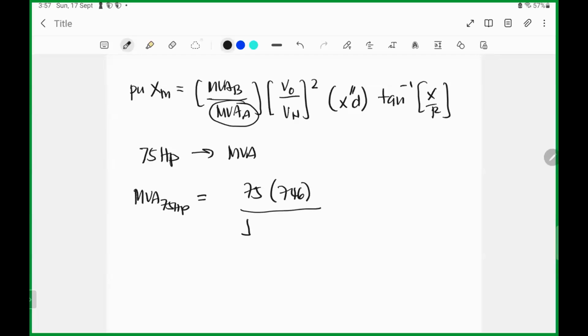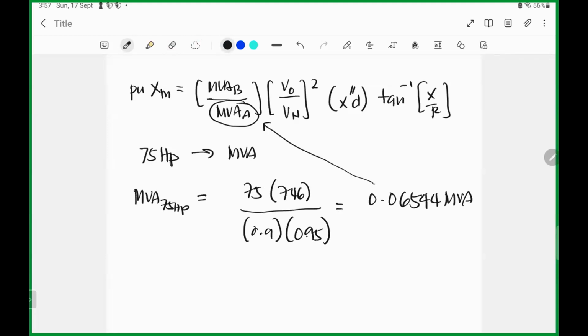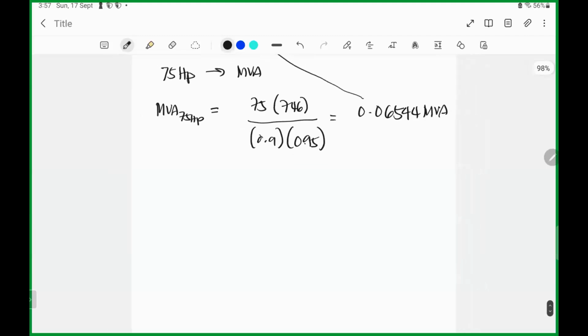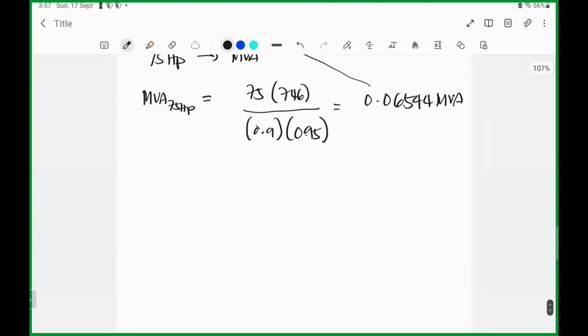oh sorry, wala pala, hindi pala current. So this will be divided by the power factor and efficiency. So you will get 0.06544 MVA. So naka-MVA ka na, pwede mo nang gamitin dito. But in the other practice, ang ginagawa ng iba, 1 kVA, 1 horsepower, 1 kVA. Pwede naman, conservative yung calculation mo.